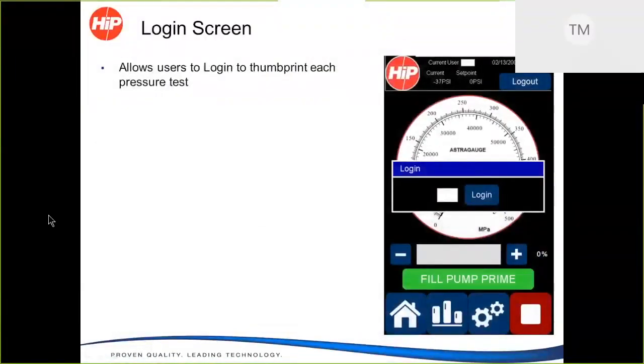So moving on, I want to go through a couple of the screens just to give you a highlight of how a user would interact with this system. When you power the unit up, the first screen you're going to see is a login screen. If you type in either a couple numbers or initials, it's a 3-digit code that you can enter in, and that'll be used as an identifier of who's running the machine at that time. So when you ultimately have that test report at the end, it's going to be able to tell you a certain user logged into the unit and ran that test.